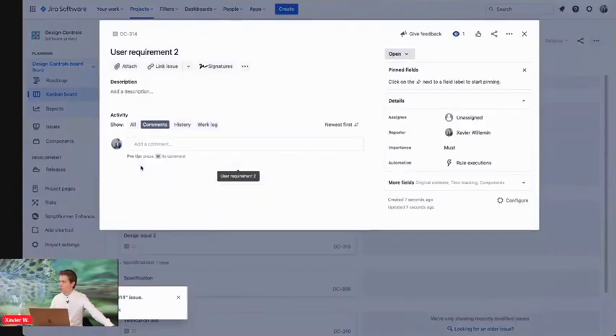From here you can link it to other parts of the design control: your design inputs, design outputs, verification tests, and then validation tests. The point is to go through the whole V model that you're used to in ISO 13485 certification, and we link each issue from one to the other.